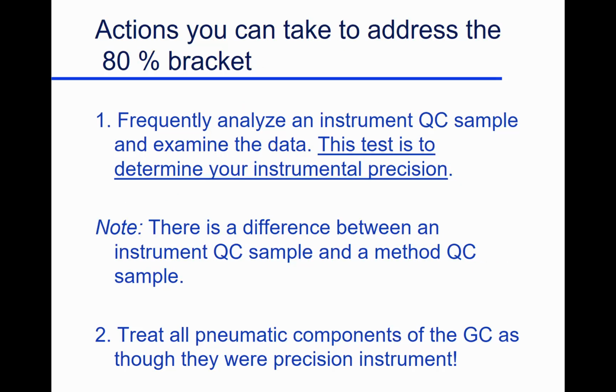How do we monitor this? Control samples. We use two types of control samples. Our first type of control sample is we'll be making injections. Typically we have a machine making the injections for us automatically. We slip in known standards, known concentration. And so the machine's running on knowns, it runs one that you made up, you know what it is. And if it isn't right, the machine's screwed up. There's a problem someplace. So you just randomly put them in your analyses to make sure the machine is running properly.